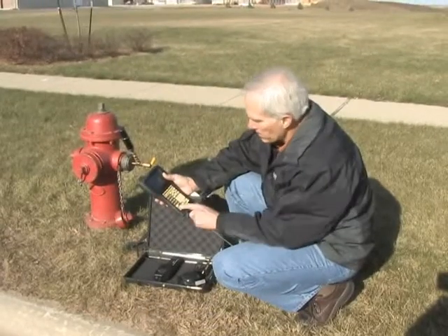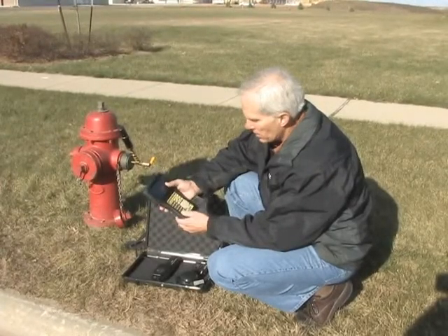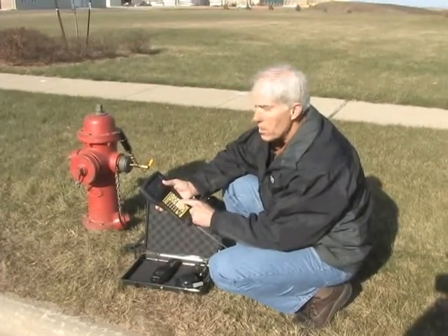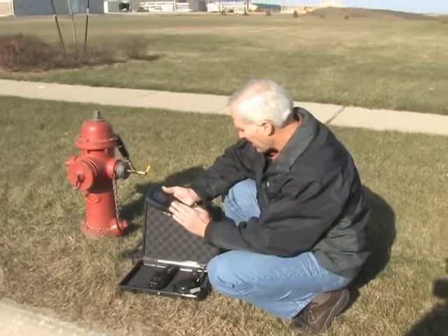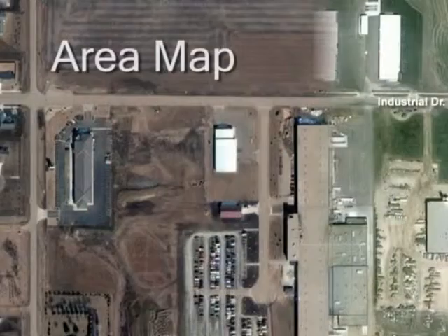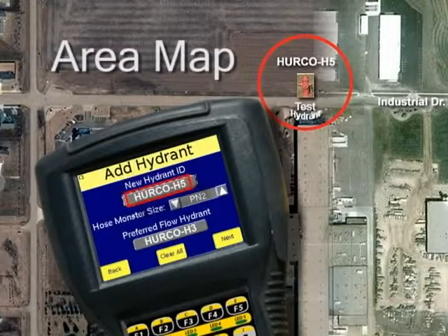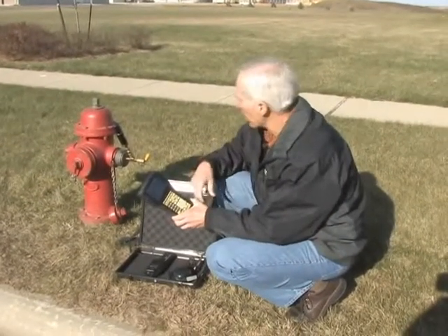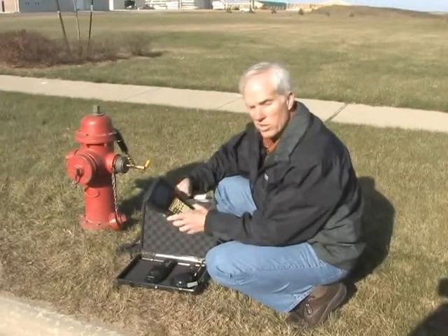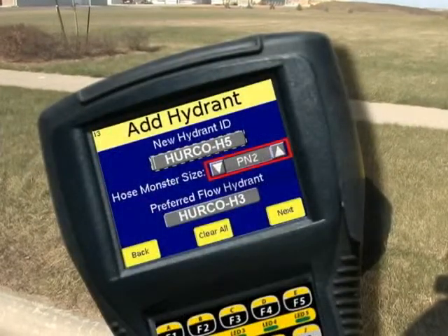I push F1 and it allows me to add a new alphanumeric hydrant. To use the alphabet side of the keyboard, I shift up — the top half of the keys then work as letter keys. To use the symbols, I shift off. The number keys always work as numbers regardless. I'm going to add an alphanumeric hydrant called HURCO-H5 for hydrant 5. The next thing is to select the size I'm testing off of, which is going to be the two-inch — we're using a two-inch nozzle working off the two-and-a-half-inch side of the fire hydrant.